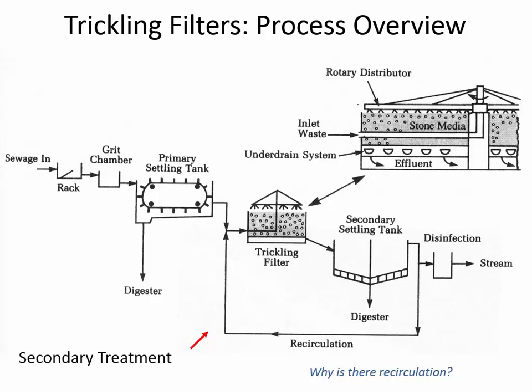So this trickling filter, you can see, has a recycle that allows us to increase the liquid contact time with the rocks. If we didn't have recycle, then the water is just going through the rocks too quickly to remove much BOD. But if it's only 1 minute and we recycle 20 times, then that's effectively 20 minutes of contact. And so you can get the idea of why the recycle is important.